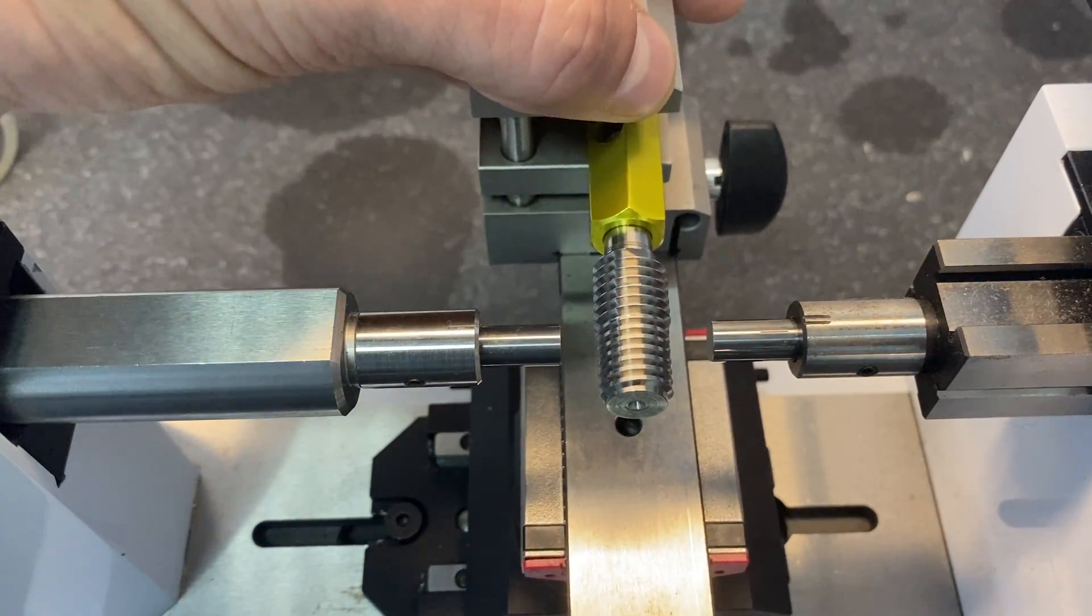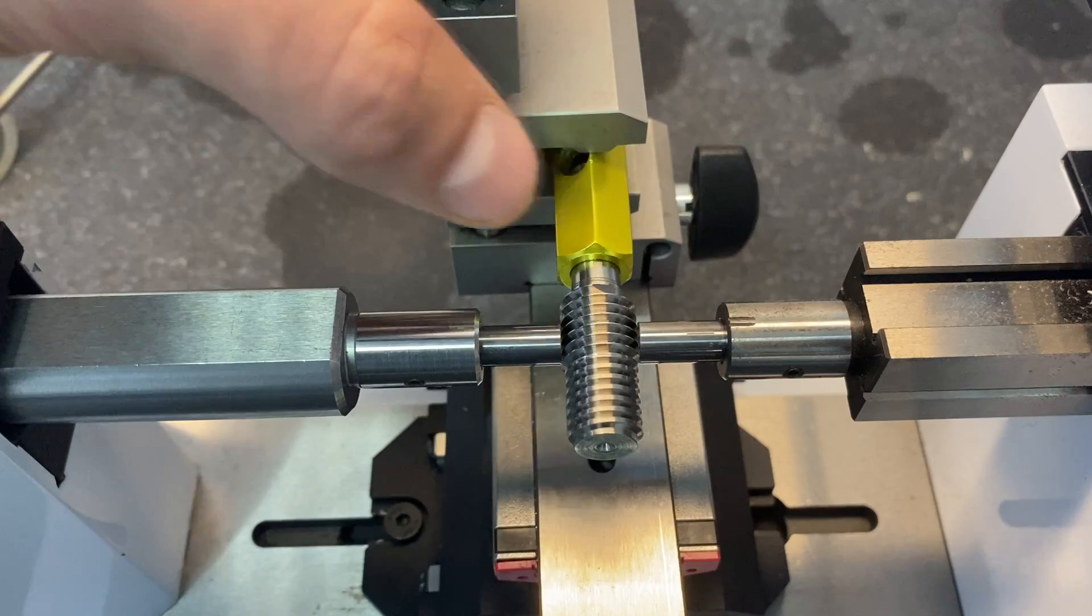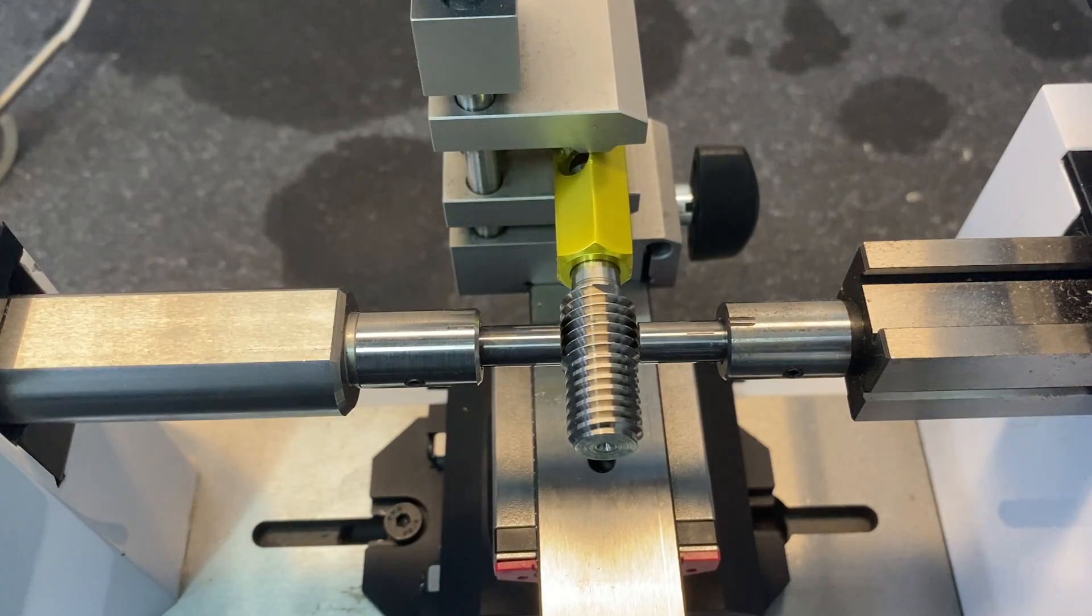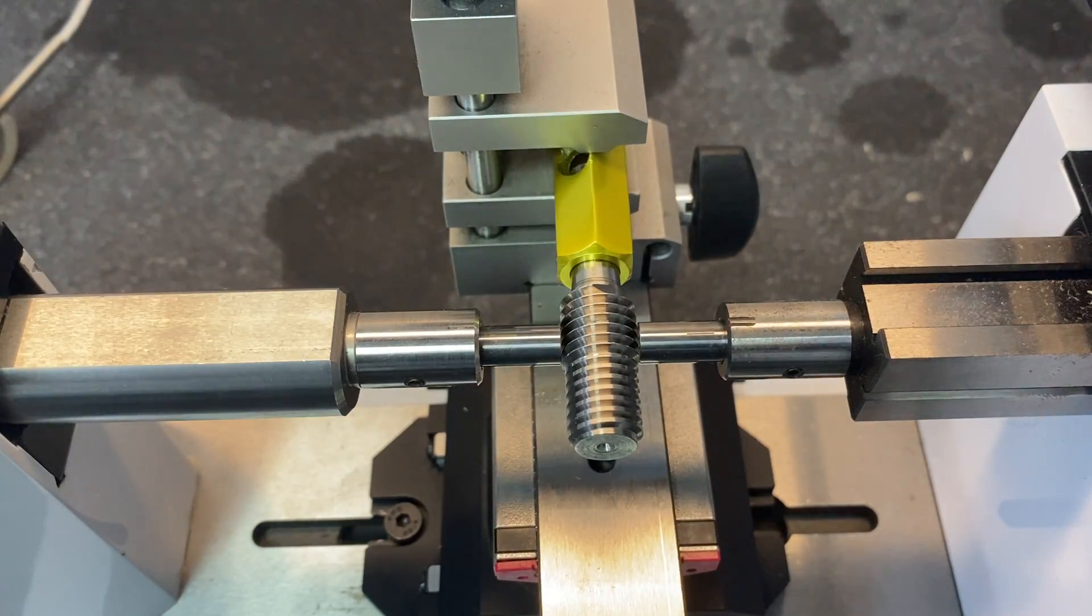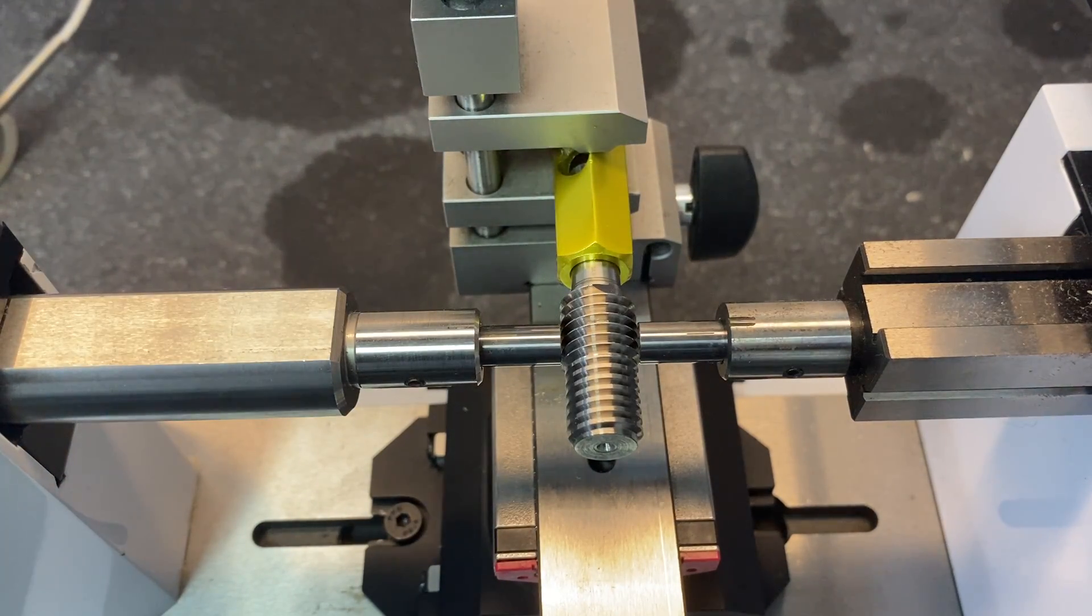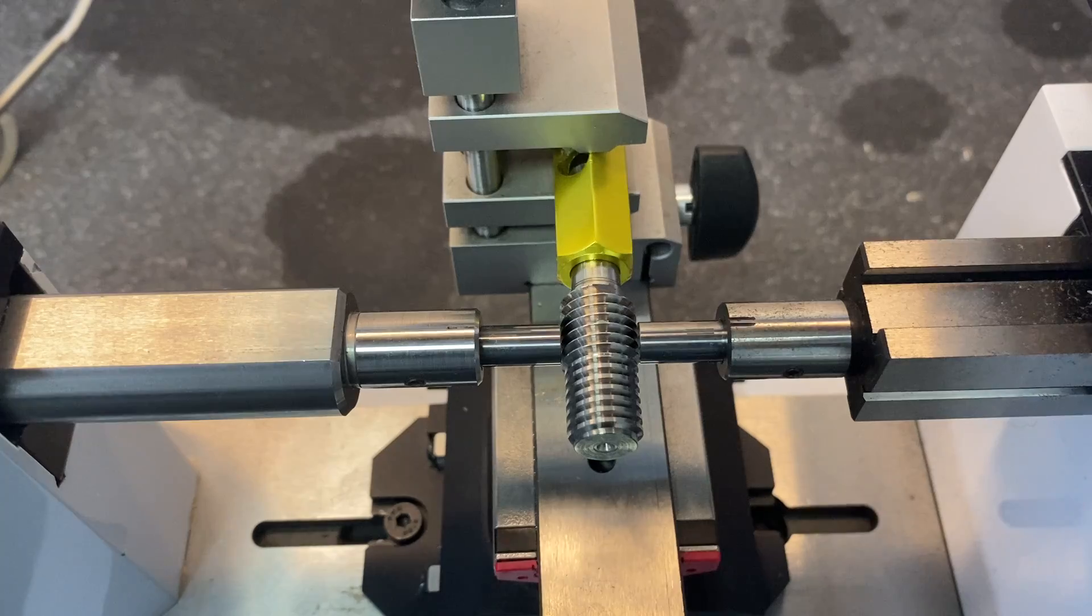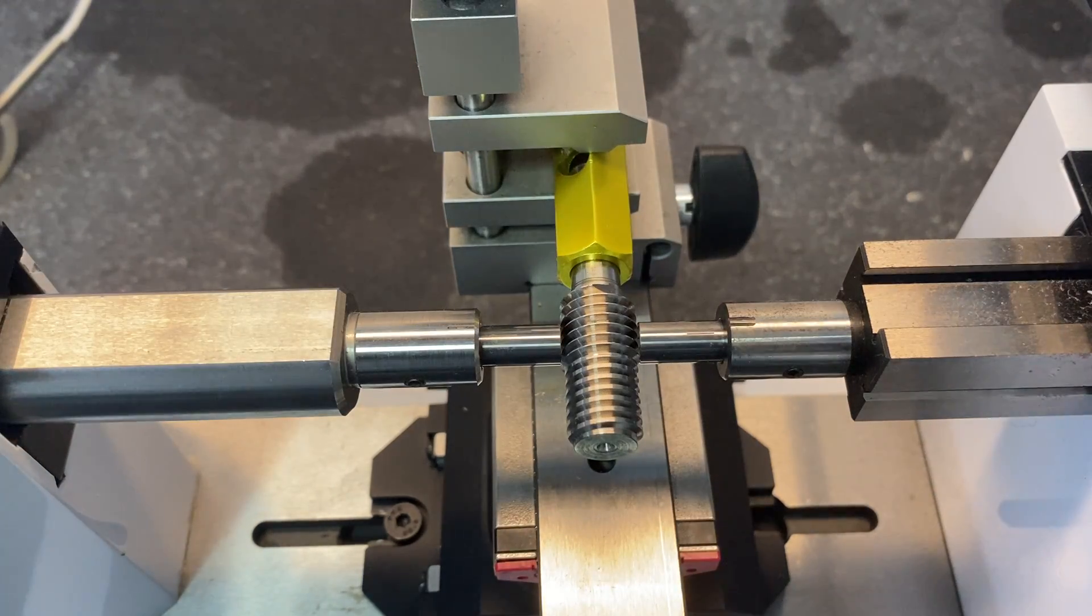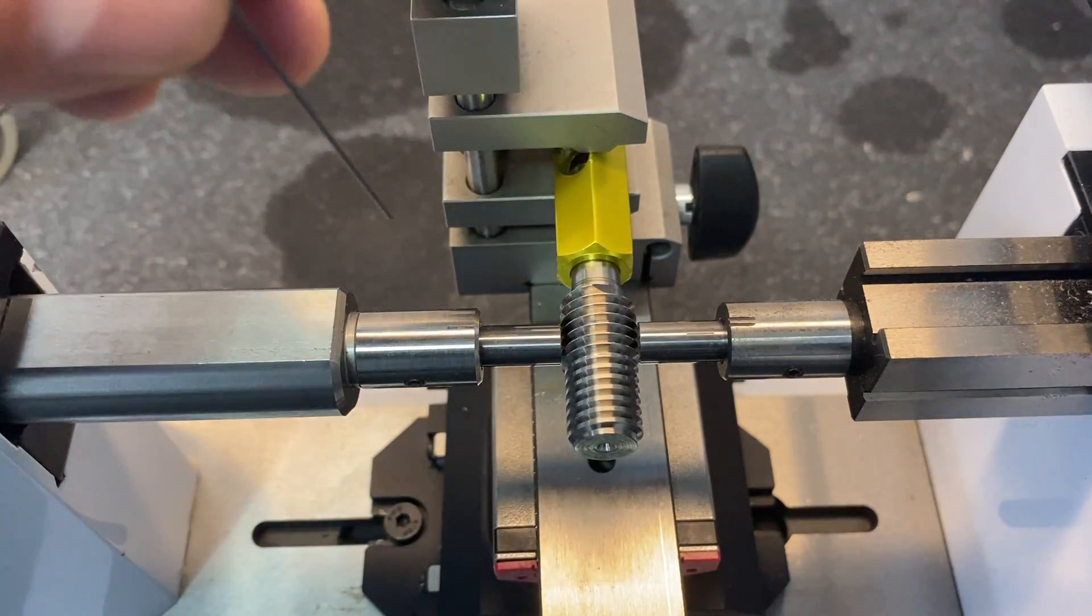And we will do the full thread for this demonstration. This will be the pitch diameter measurement using the three-wire method. So position the thread in between the anvils.